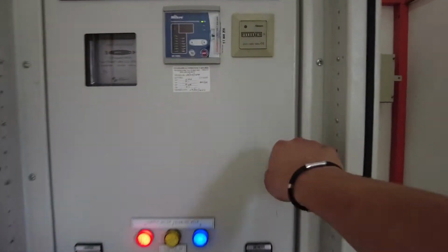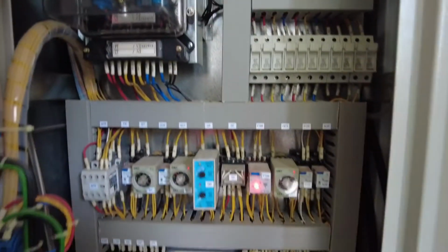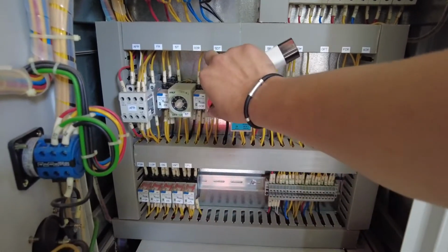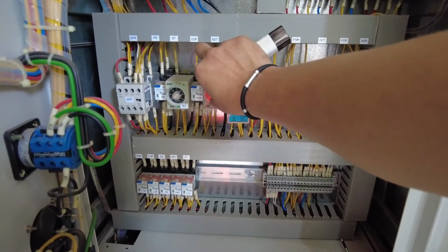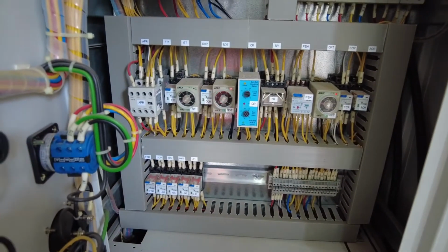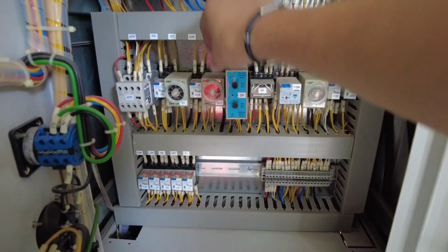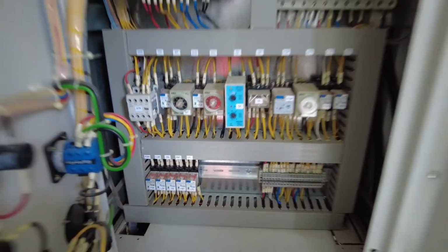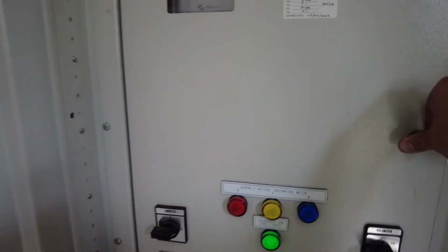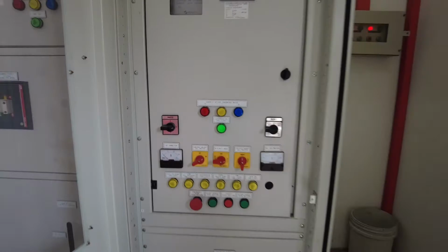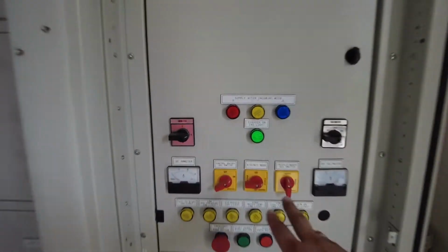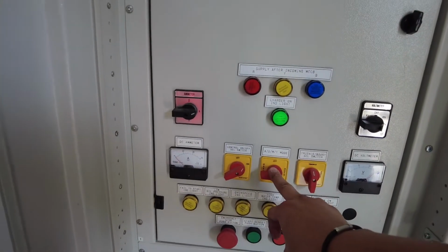Okay, we allow it to stop automatically. The shutdown timer is 3 minutes. We fasten it up. Okay, now it stopped. Okay, because I turned the shutdown timer to fasten it. Okay, now we already test under test mode, manual mode, and now we're going to test auto mode by simulating the signal here.